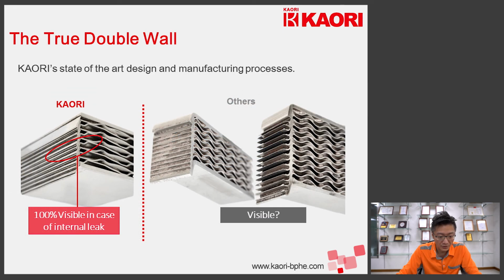Let's take a look at the cross-section of the double wall brazed plate heat exchanger and make a quick comparison between Kaori's double wall and others available in the market. In Kaori's double wall, each plate has sufficient clearance in between, so the leakage will be 100% visible from outside. With the others available in the market, there is not much clearance between the plates, so the leakage is not always visible from outside.